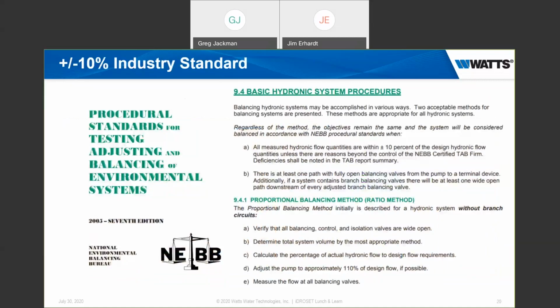The National Environmental Balancing Bureau produces the procedural standards for testing, adjusting, and balancing environmental systems. This applies to both the air side, because a typical system is going to be a fan coil with ductwork that's either getting chilled water from chillers circulating through it or heated water from boilers circulating through it. So the commercial system has 2 sides. It has the air side and it has what we'll call the wet side. And the NEBB standard here covers both the air side and the wet side.